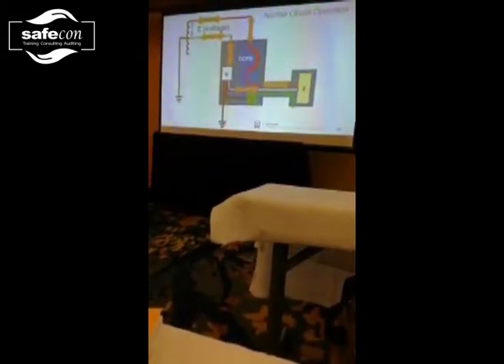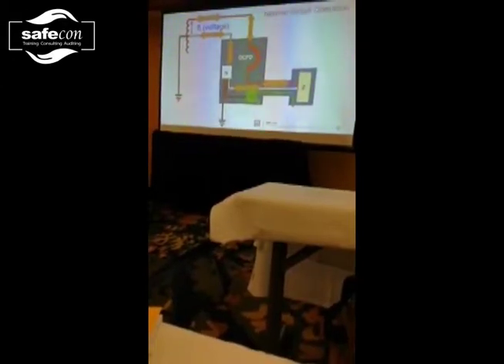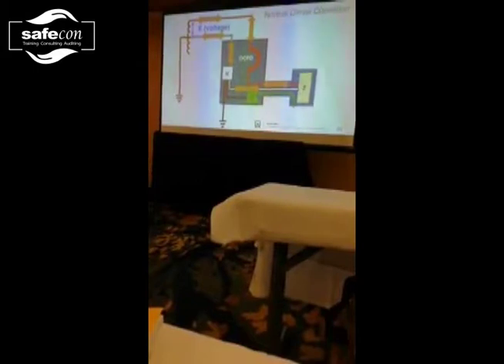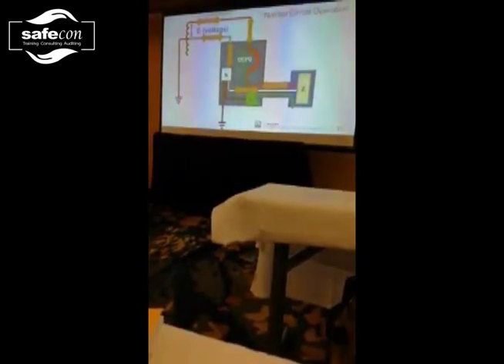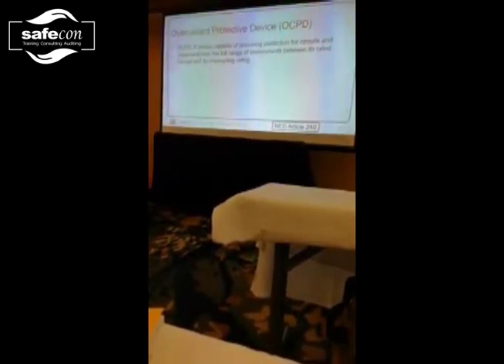So again, you can see the normal pathway, the normal flow of the circuit, with the impedance actually being the load. So on the lighting circuit in this room right now, the actual current flow is determined by the load, right? It's determined by the ballast or the drivers in the luminaires or incandescent lamps, whatever they are. It is governing the actual amount of current flow normally in the circuit. So that's the normal circuit operation. So the overcurrent device obviously protects the circuits and the equipment.